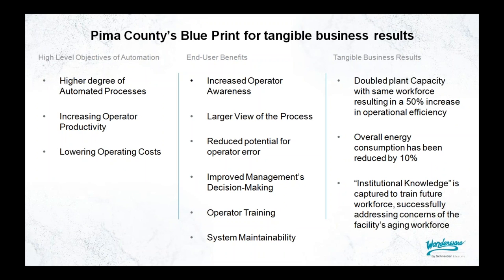The other was the implementation under the hood of advanced process control, model-based control for things like chlorination and dechlorination, most-open valve control, or advanced blower and aeration control. Ammonia destruction control is available if we want to use it, and we also have nitrate control. So in other words, we have a lot more advanced control than we formerly had. We've raised the bar on what we can do in order to achieve A-plus quality water production.